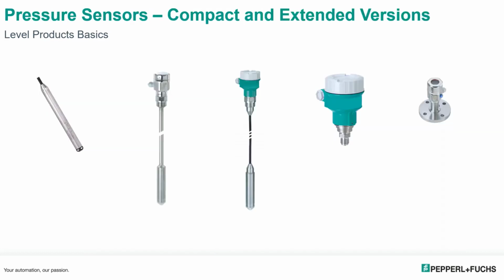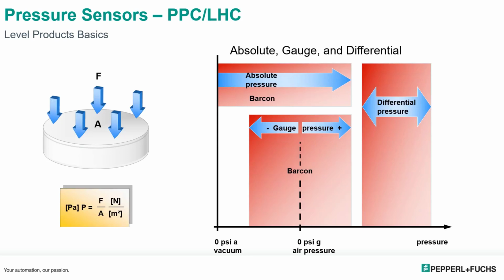Another type of continuous measurement probe we offer is the pressure sensors. We have them in a compact version, extended versions, cable versions, rod versions, and process connection versions as well. The pressure probes use a piezo element on the face of the sensor, and as force is exerted on this, it produces a signal, and we convert that to a workable 4 to 20 milliamp and so on. They can measure absolute pressures and gauge pressures as well.